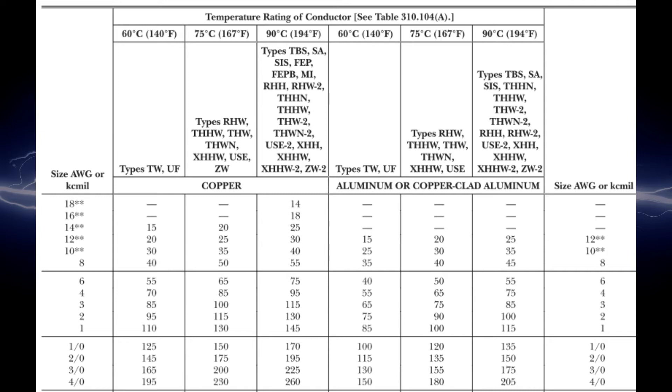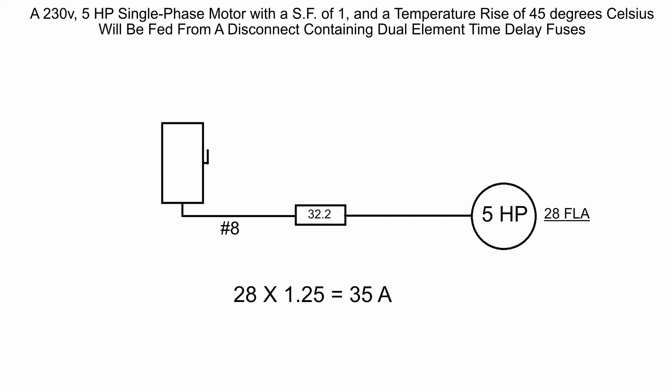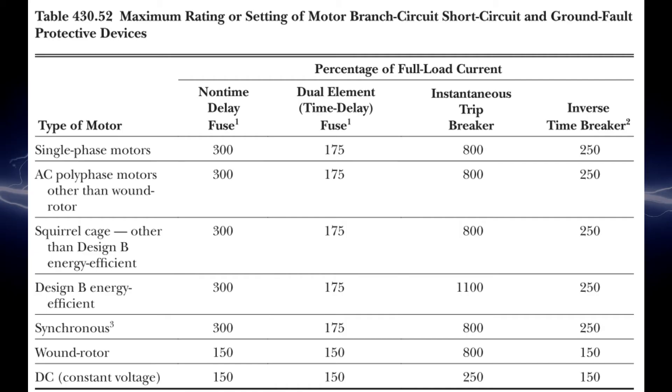The final phase in this problem is to solve the overcurrent protective device. Again, there's more information that's very important. We were told that the disconnect will contain dual element time delay fuses. To size this overcurrent for the motor we will go over to Table 430.52. This is for all of your motor sizing for the short circuit and ground fault protective devices.